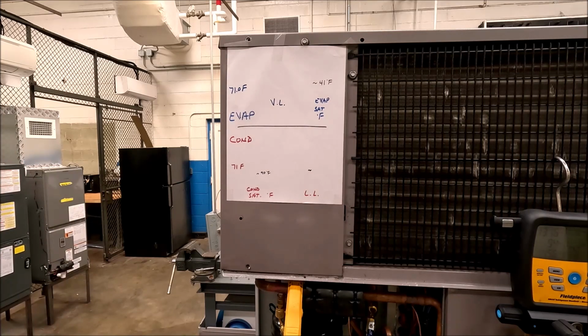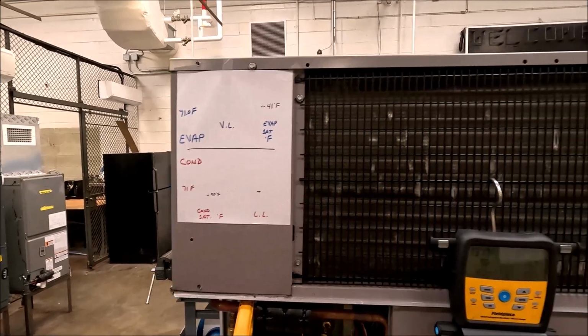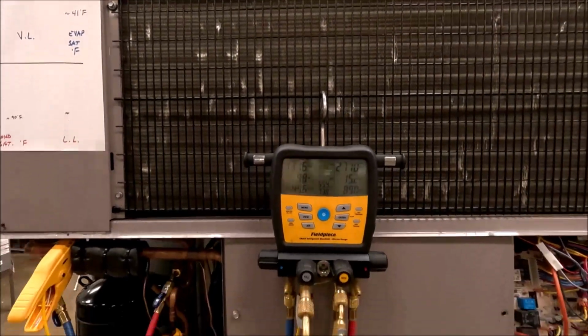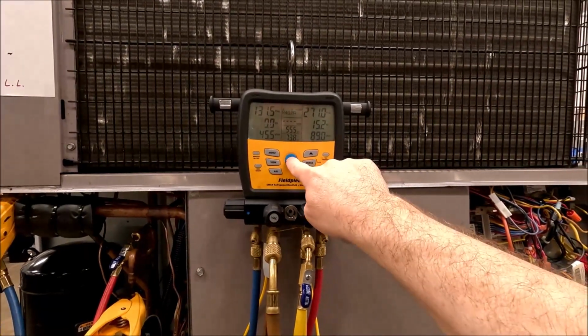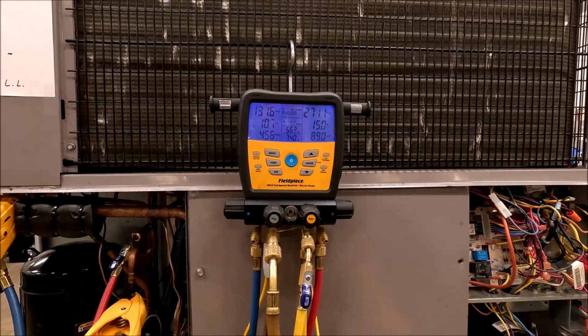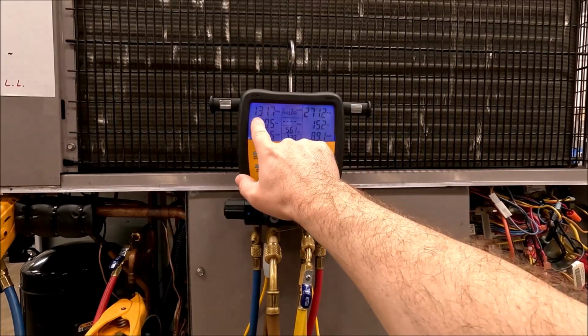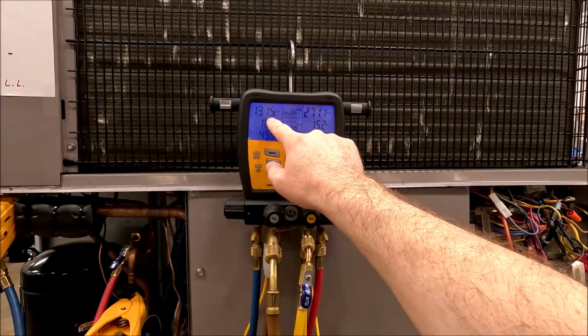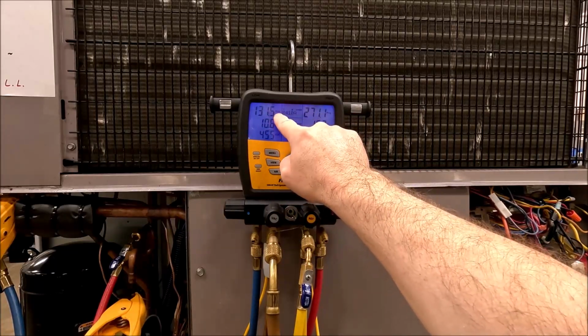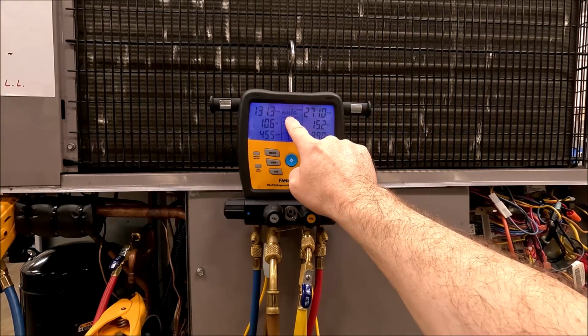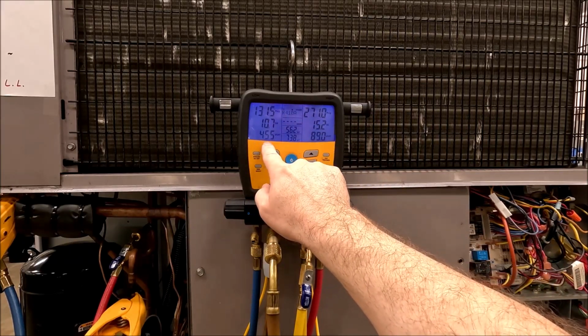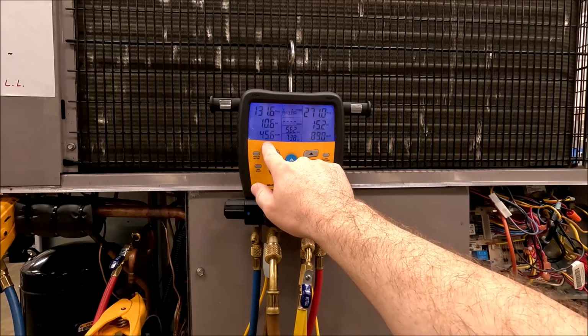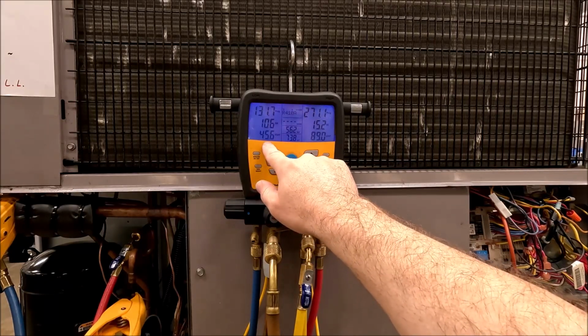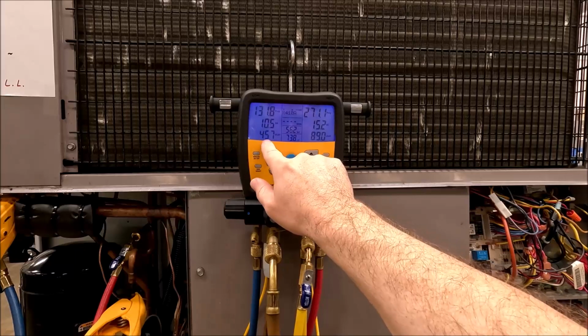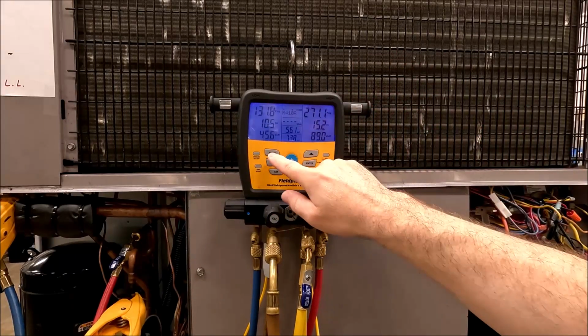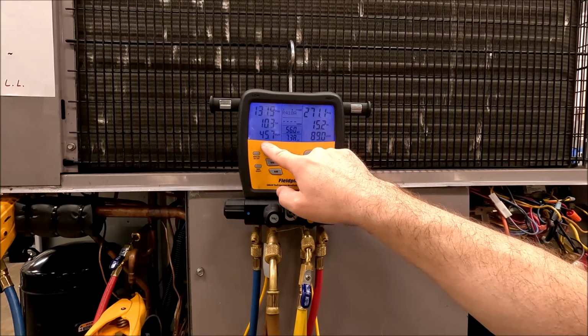All right. So, and if we look at this one, it's just too pretty on this one. As we look at this one, there we go. You can see that we have on our low side, we have 100 and almost 32 PSI. The saturation point for that pressure for 410 is going to be 45.5. Now we expected about a 41. We're a couple degrees warmer, so you know, give or take a degree. I mean, we're in the ballpark. To me, we're better off than the other unit. We were low on that other unit. We were in the 30s, 35.